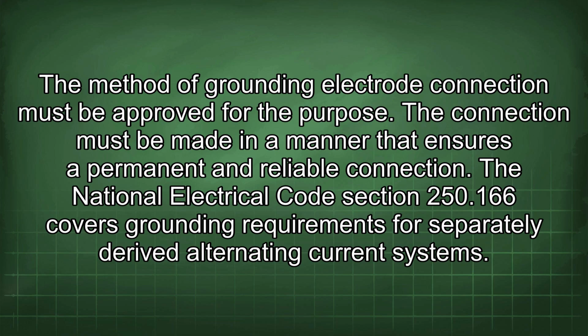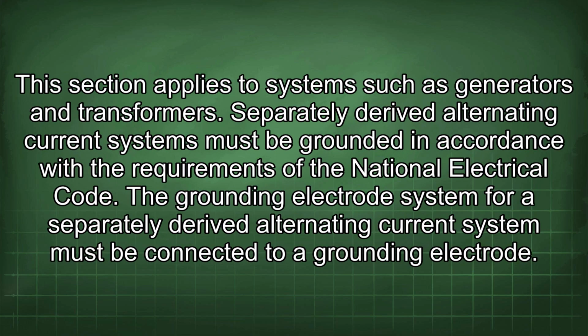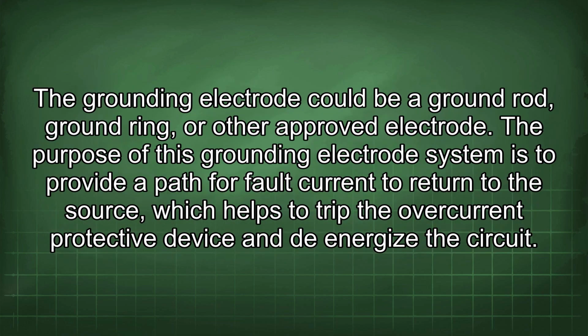The National Electrical Code Section 250.166 covers grounding requirements for separately derived alternating current systems. This section applies to systems such as generators and transformers. Separately derived alternating current systems must be grounded in accordance with the requirements of the National Electrical Code. The grounding electrode system for a separately derived alternating current system must be connected to a grounding electrode. The grounding electrode could be a ground rod, ground ring, or other approved electrode.